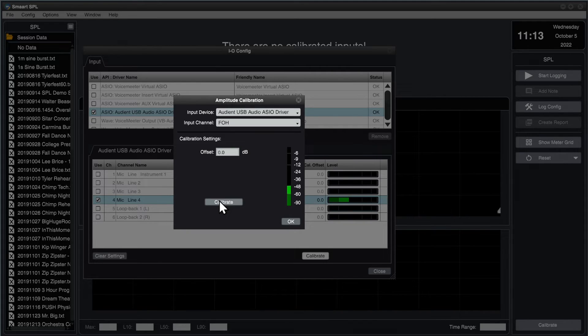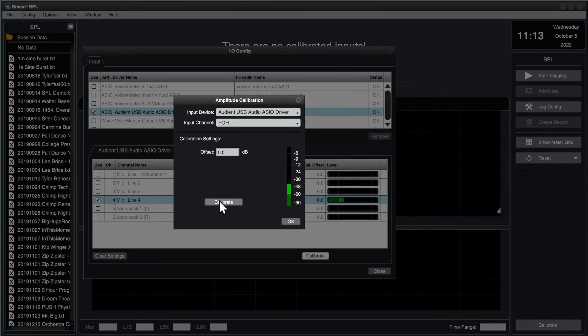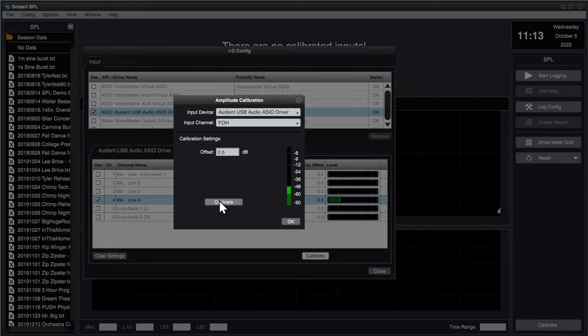Turn on your sound level calibrator and carefully fit it over your measurement microphone, using the proper coupler diameter for your measurement microphone and ensuring a proper seal.